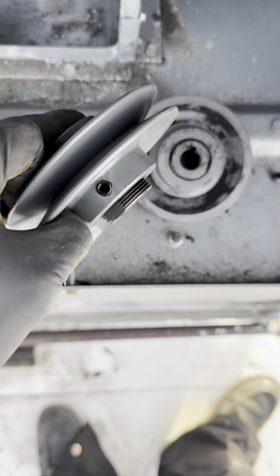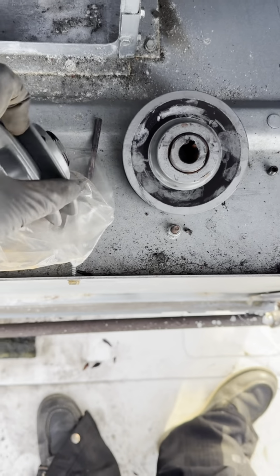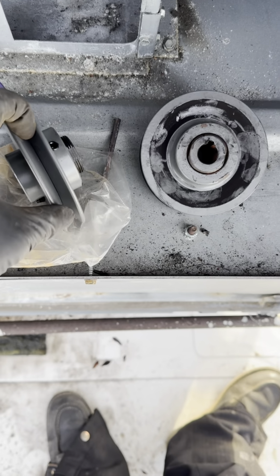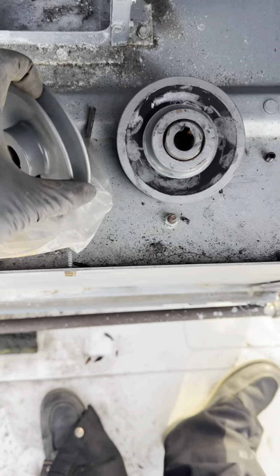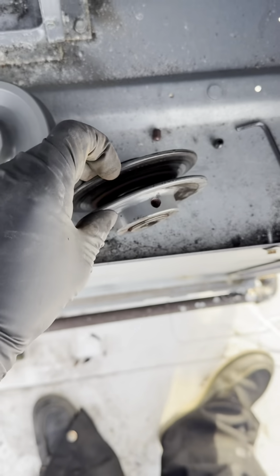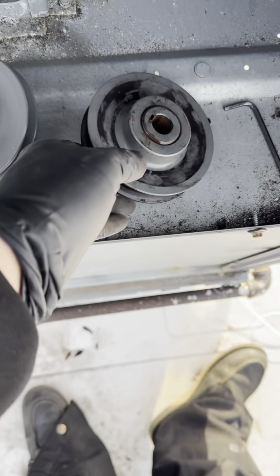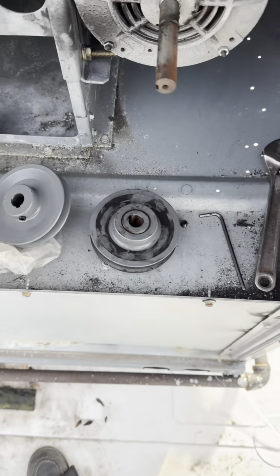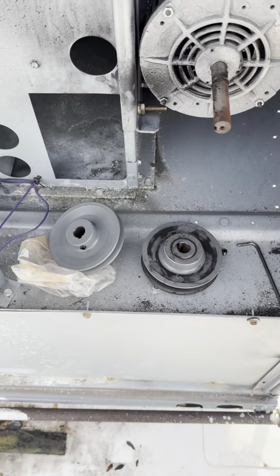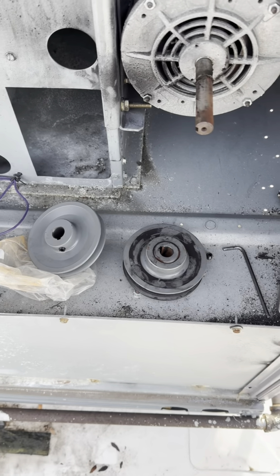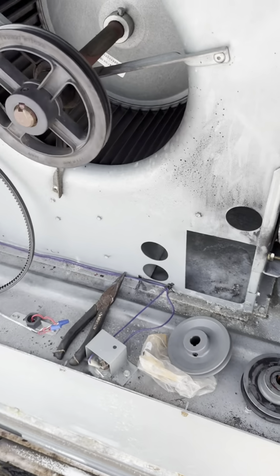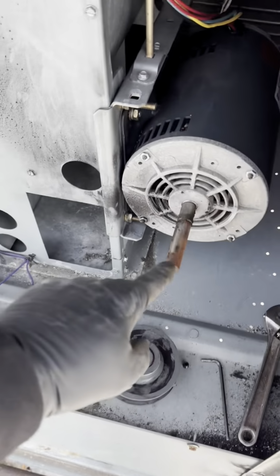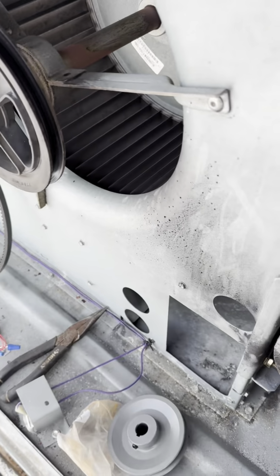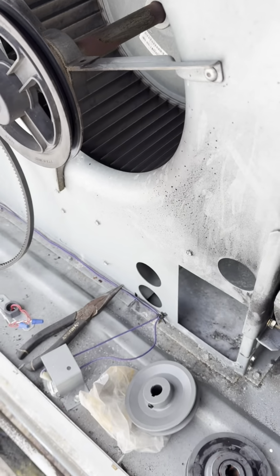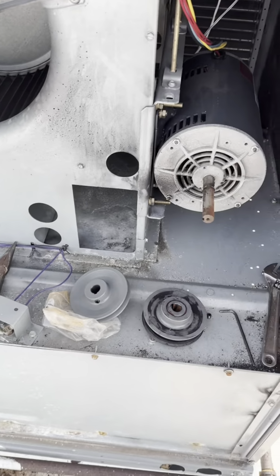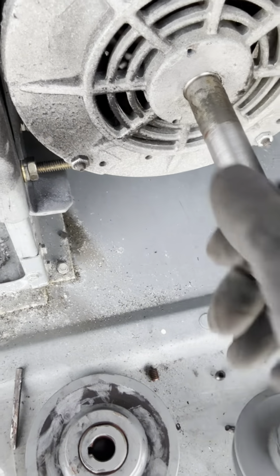We're going to put that in, adjust the adjustment on the pulley to kind of match this one, but we'll always have to take an amp reading after we're done so that we make sure that the amps are within the motor spec. And also we're going to adjust the belt tension and make sure everything aligns properly. Stay tuned. Shaft is cleaned up.